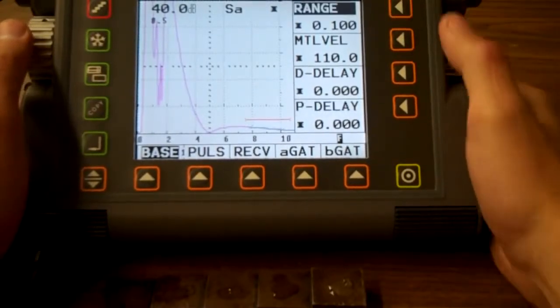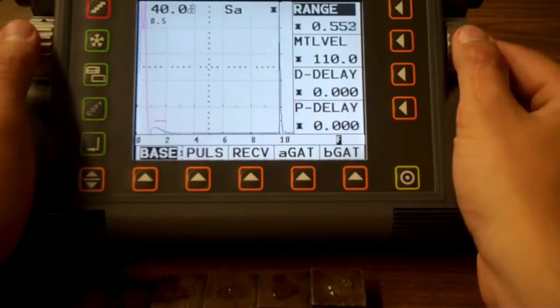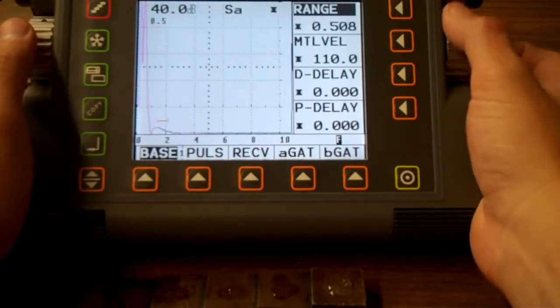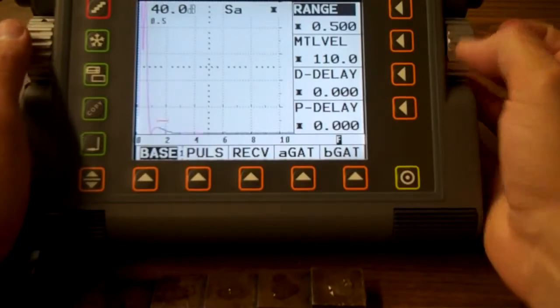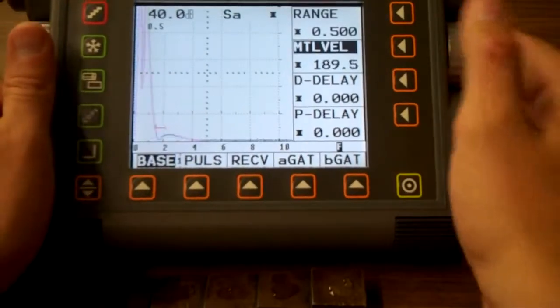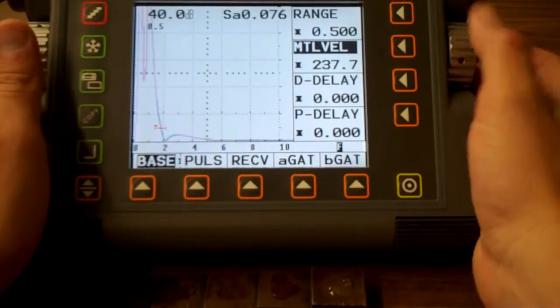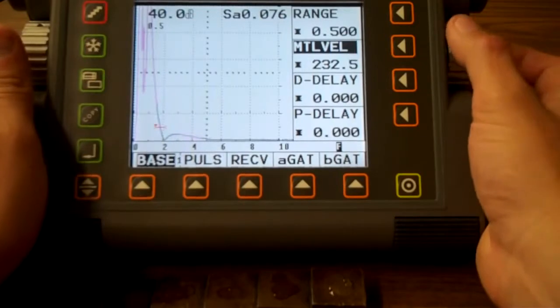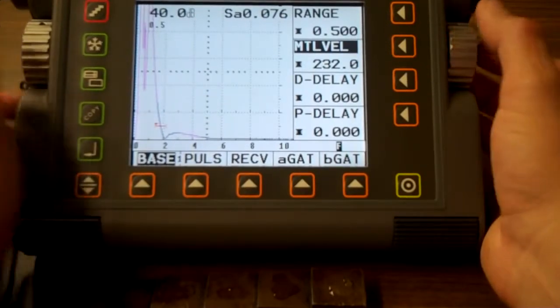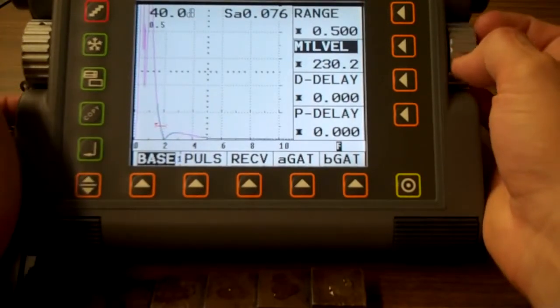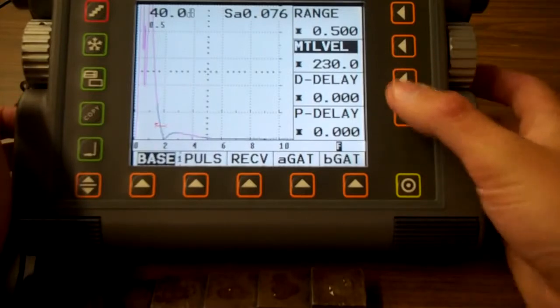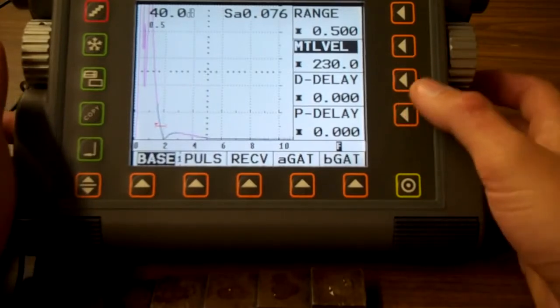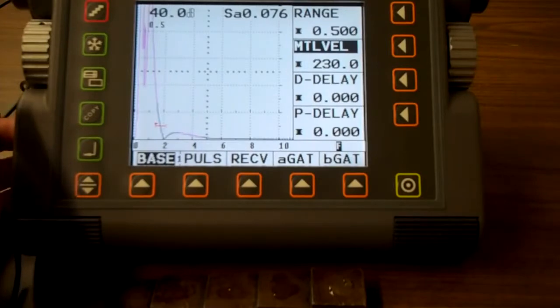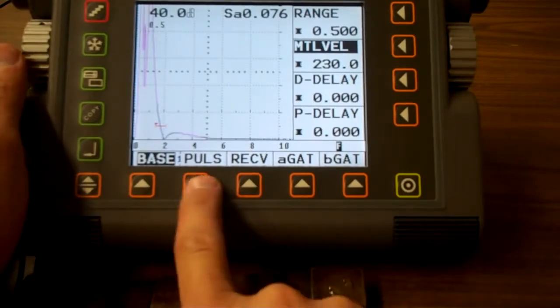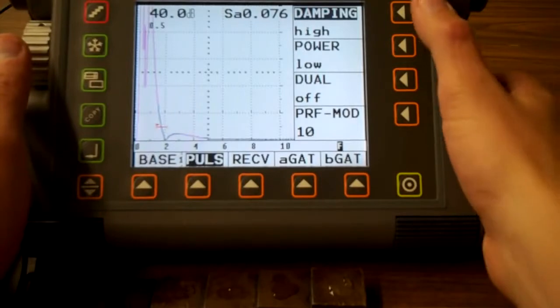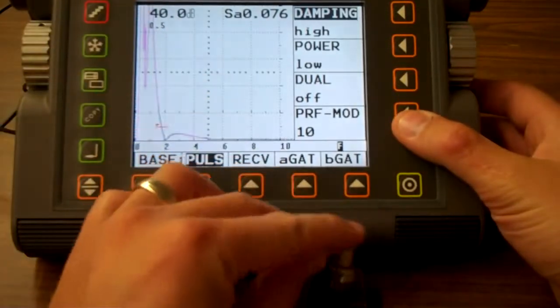First things first, I'm going to change my range to 0.5. There it is. Material velocity 0.23. But in this case, you got to go to a 232 or 230 either way. USM 35 is a little different. Display delay, probe delay. I'm personally right now going to use probe delay since I'm using a delay line transducer. That helps build in where I need to be. So we'll come back to this.